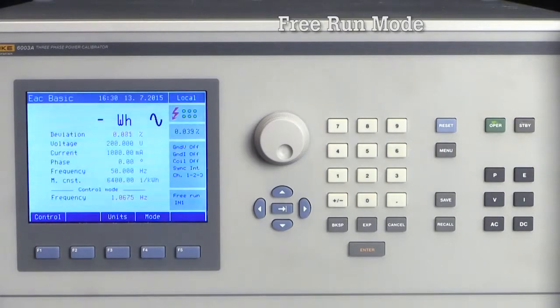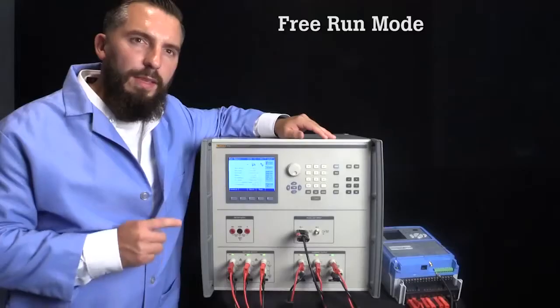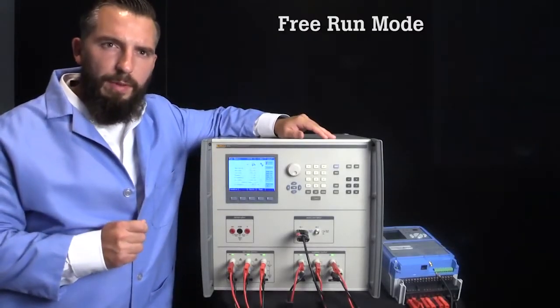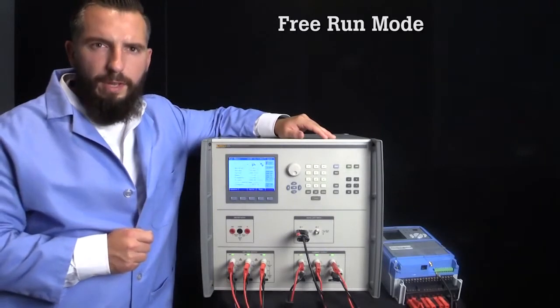The meter we are testing is a three-phase class 0.2 energy meter and, based on this measurement, the meter is well within that specification window. This mode is useful for troubleshooting setups and is not recommended for the most accurate and repeatable energy calibrations.